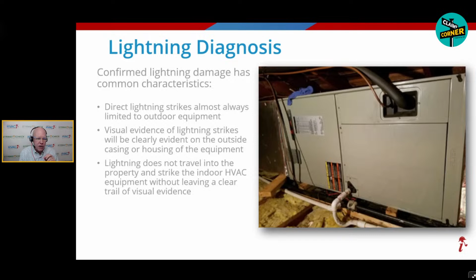Solenoids are connected by low voltage wires. The energy now gets into the system through the wires and goes other places, and it causes lots of other damage. When that energy travels inside, we would expect it to leave a trail of evidence. With surge, maybe not so much until it gets to an endpoint. With lightning, there are a couple of different ways you could look for it. One would be arcing. Again, there's so much energy in lightning, it's got to end somewhere. It's got to dissipate. And when it does, it usually leaves visual evidence more so than surge. Surge still can, but lightning more so.